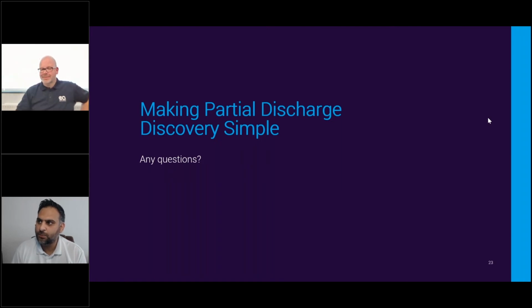The first question is, what does PD smell of? Surface PD or ultrasonic PD, when it starts to initiate, usually manifests itself as ultrasonic noise. But if it gets bad enough, it will cause generation of ozone. That ozone typically smells like chlorine or bleach. It's a very sharp smell. So if you are entering a new substation that you haven't been to before, and you smell this very sharp smell, that is typically an indicator that you've got partial discharge activity within the switchgear. So you need to be very careful. If it's bad enough, then you need to carry out a risk assessment of whether you should be within the substation or not, and whatever operation you need to do, just be careful with it.